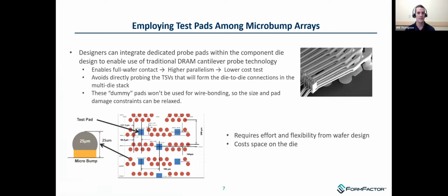Well, so these test pads, the ones that we typically see are about 40 to 50 micron. I mean, these are high density arrays. And so people don't go crazy with it, making big pads everywhere. But if possible, the idea is to make it as large as you will be allowed, right? A part of the engineering challenge too is that the probes have to be elongated slightly to reach over the bumps. So it does require a bit of give and take and conversing with your probe designers and between wafer designers.